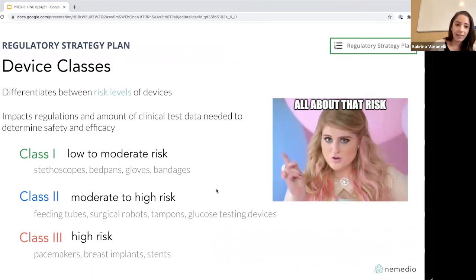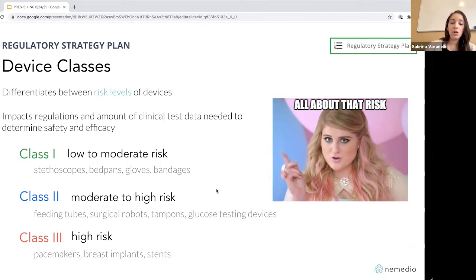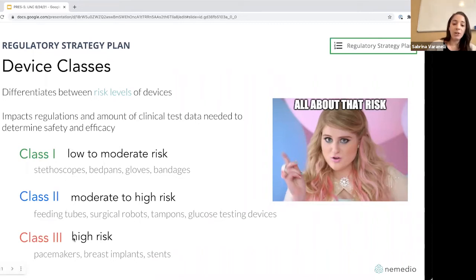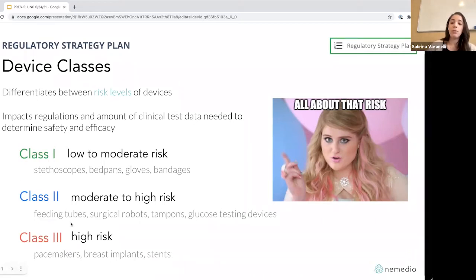Diving into the regulatory strategy plan: one of the most critical things is the concept of device classification, or device classes. The FDA divides products based on their risk level. Class one is lower risk, class two is moderate risk, class three is high risk, and most devices end up being class two — moderate to high risk. Depending on your classification, you have minimum requirements for study submission and data submission that you have to do in order to get your device cleared. Device classification also informs what types of regulations you need to follow from a quality system perspective, and the types of standards you should be following during engineering.